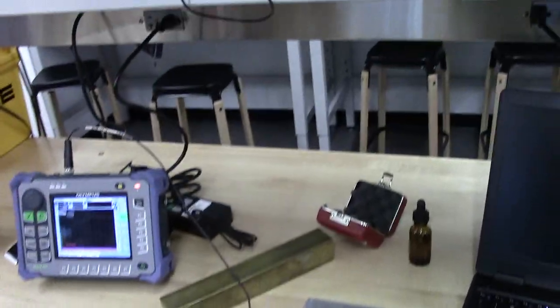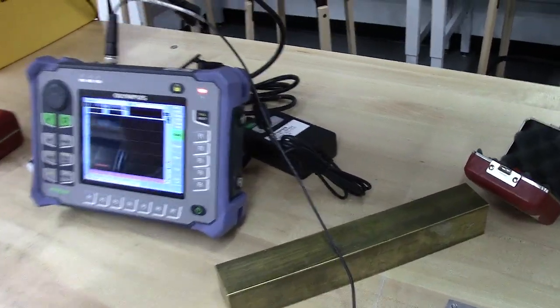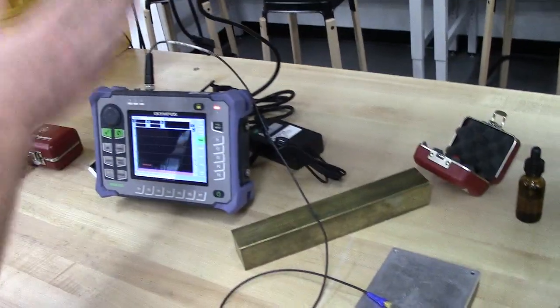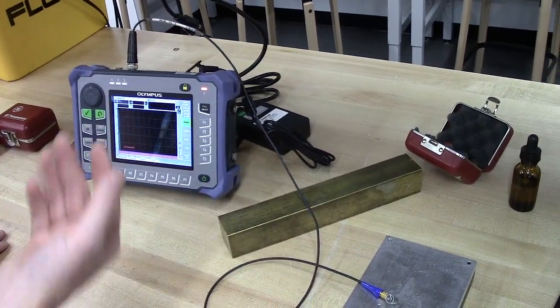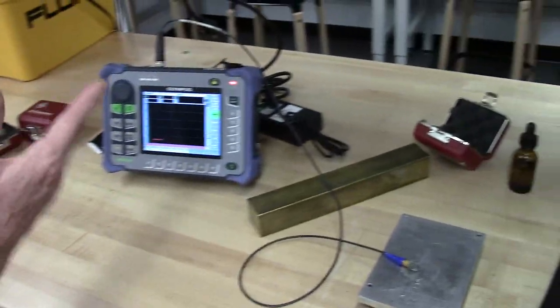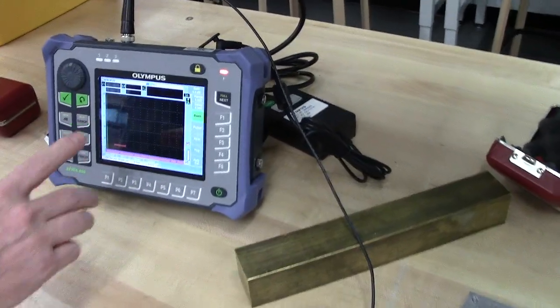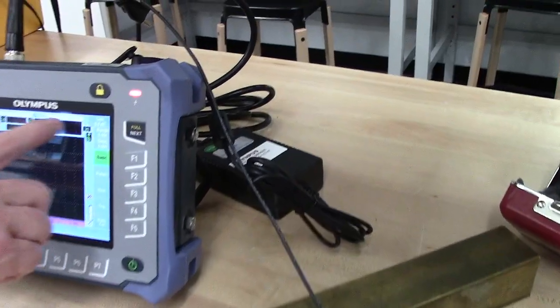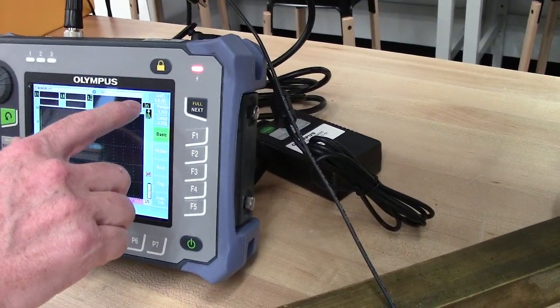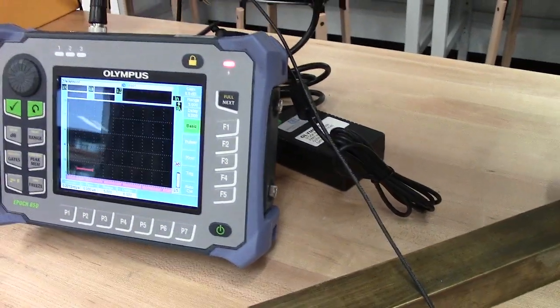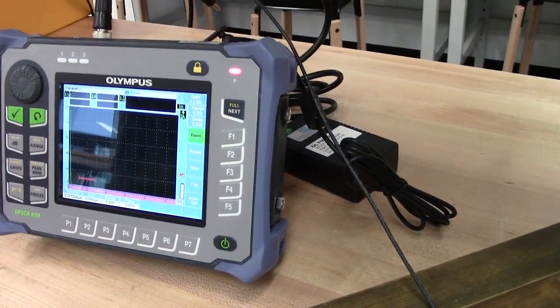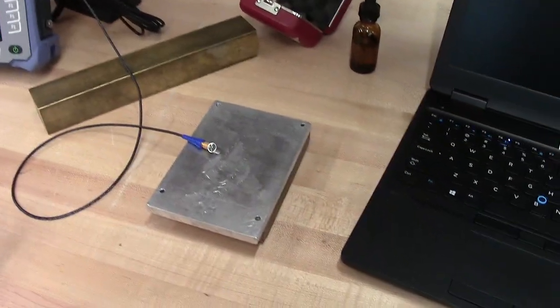We need to make some adjustments over here. So this is reset to factory defaults. You might get lucky and come in and have one that's kind of set up for you from the previous group. Or we might reset it. You might need to do this from the beginning. But just to show you how to do it from the beginning. The first thing, note up here, this is where we're going to get our measurement out. And note the units are inches. And again, there are lots of different ways we can set this up. But what we're going to try to determine first is the longitudinal wave speed.